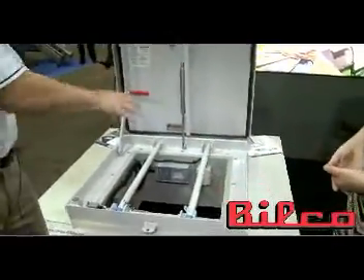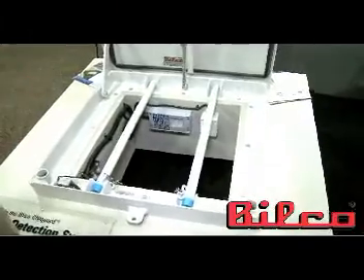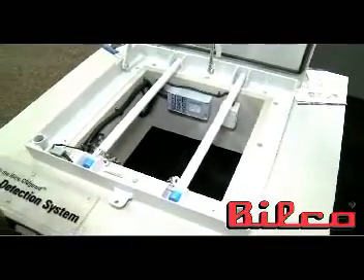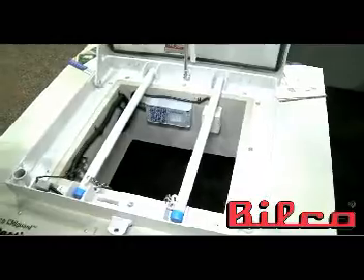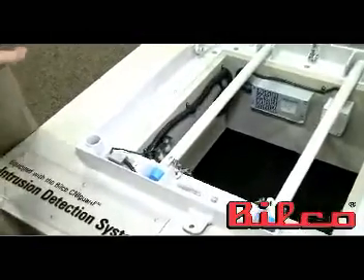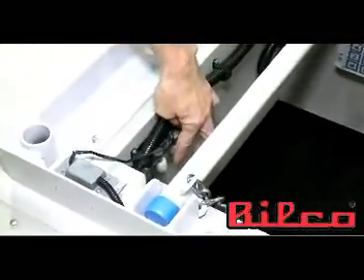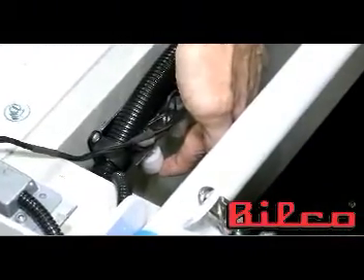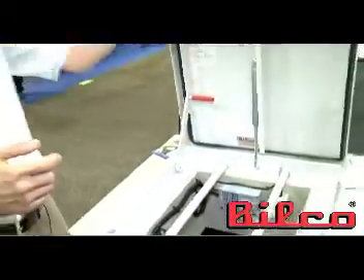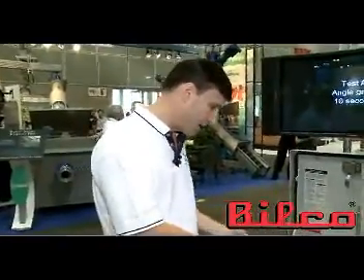Now the other thing about the system, it's not only just for security, it can also help in process control. So one of the things that you might be concerned about is if there's, let's say, expensive equipment inside here, like a pump or instrumentation, then you might be concerned about flooding. If there's flooding inside here, I want to know about it very early. So one of the things that we've put on here is the ability to put other sensors. That's why we call it a smart sensoring technology, because you can put other things that are relevant. So for example, here, these are called float sensors. And if you activate these, it again generates an alarm, and that means that there's now flooding inside here. Now the operational manager can see, oh, I have flooding over here, send someone there, and maybe plug up the leak or take some other sort of action.